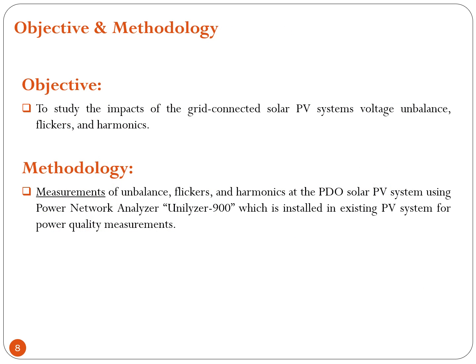The main objective of the paper is to study the impact of grid-connected solar PV systems on voltage unbalance, flickers, and harmonics. The measurement of unbalance, flickers, and harmonics at the PDO solar PV system uses a power network analyzer, which is installed in the existing solar PV systems for power quality measurement.